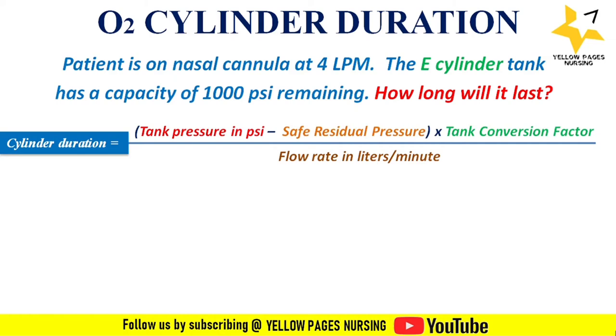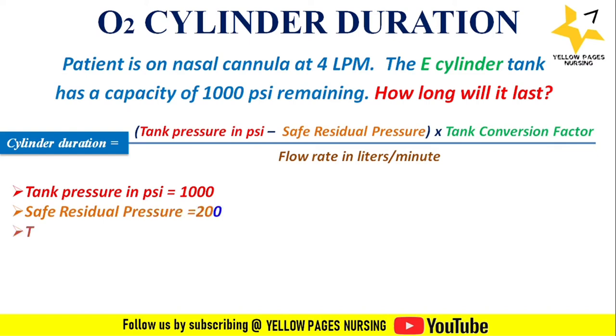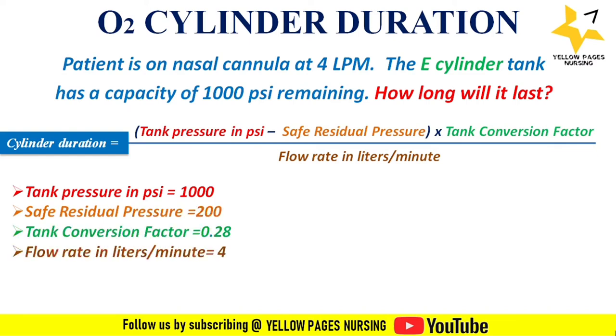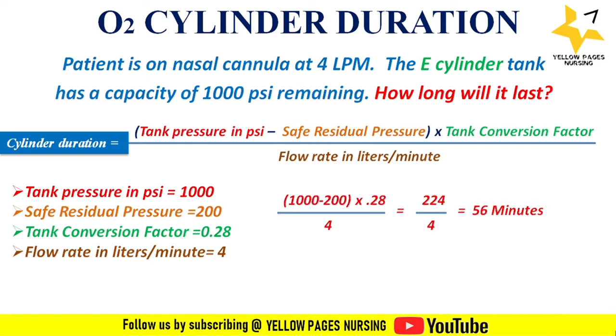Here, tank pressure in PSI is 1000, safe residual pressure is 200, and the tank conversion factor for the E-cylinder is 0.28. Flow rate in liters per minute is 4. Applying all values into the formula, we get the answer: 56 minutes. Hence, the cylinder will last for 56 minutes at a flow rate of 4 liters per minute.